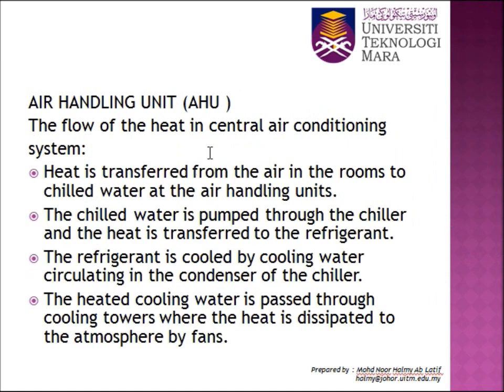The flow of the heat in central air conditioning system. Heat is transferred from the air in the rooms to chilled water at the air handling unit, or AHU. The chilled water is pumped through the chiller and the heat is transferred to the refrigerant. Okay. Then the refrigerant is cooled by cooling water circulating in the condenser of the chiller.